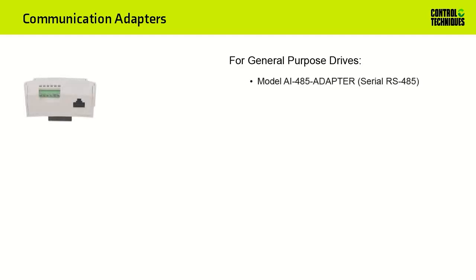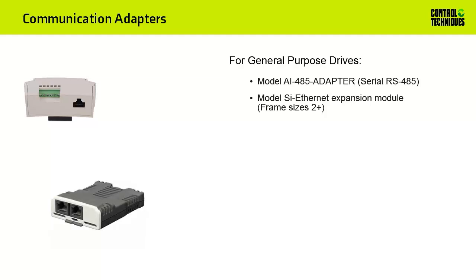For general-purpose drives, you'll require a model number AI-485 adapter to perform serial RS-485 Modbus communications using Modbus RTU. General-purpose drives, frame sizes 2 and larger, have an expansion slot that can accommodate a SI Ethernet module. Adding this module to a general-purpose drive will enable Modbus TCP-IP communication.